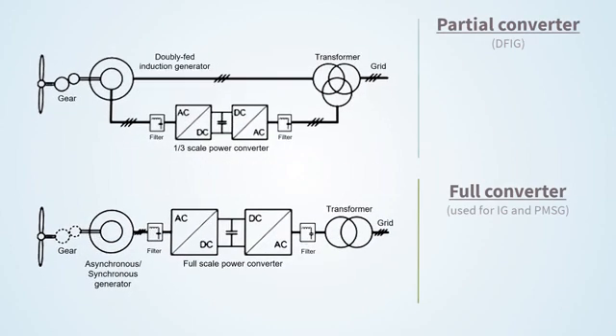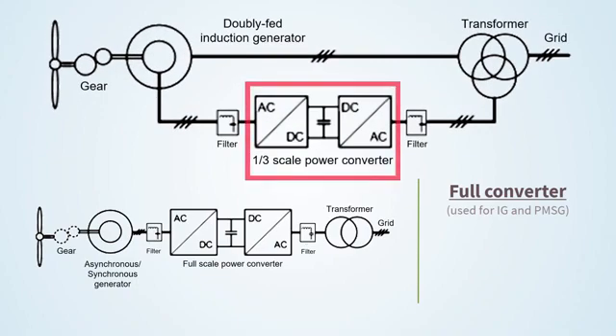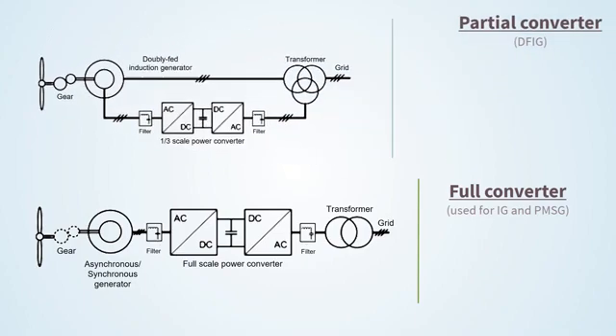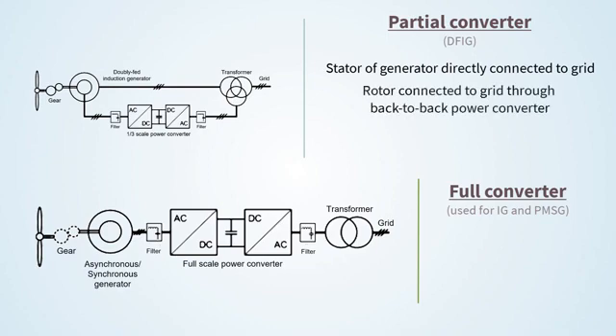Here you can see the electrical structures of the most frequently used wind converter topologies. The partial converter or DFIG, doubly fed induction generator, where the stator of the generator is directly connected to the grid and the rotor is connected to the grid through a back-to-back power converter.